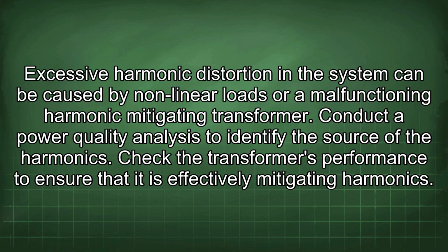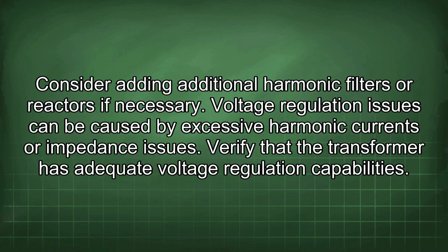Excessive harmonic distortion in the system can be caused by nonlinear loads or a malfunctioning harmonic mitigating transformer. Conduct a power quality analysis to identify the source of the harmonics. Check the transformer's performance to ensure that it is effectively mitigating harmonics. Consider adding additional harmonic filters or reactors if necessary.